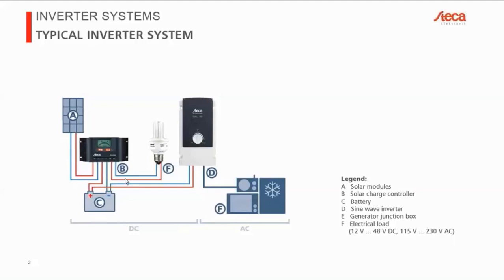This current measurement is optimized for DC loads. So here we have 100 pulses basically per second that are going towards the inverter. So this current measurement is not able to keep up with that. So in other words, your current measurement will be off towards the inverter, and that will simply mean that your state of charge calculation will also be off.